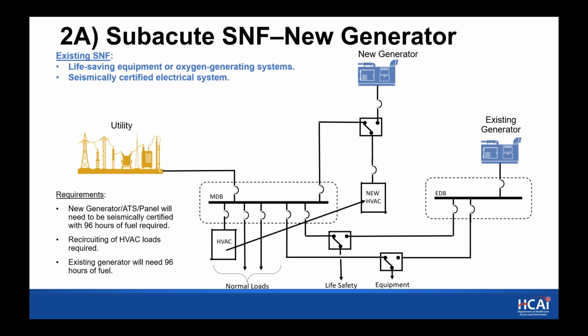assumes that you do have life-saving equipment or oxygen generating systems because it is a subacute SNF, and you are dealing with a different population there. So in that case, we would assume that the existing generator feeds red plugs that are in patient rooms and in areas that would support the life-saving equipment and oxygen generating systems. And if you're counting on that to be your backup source for the life-saving equipment, and your existing system provides that, now that existing generator would need to have provisions for the 96 hours.